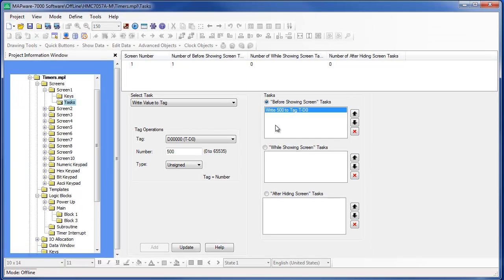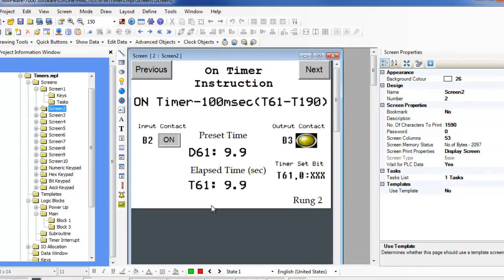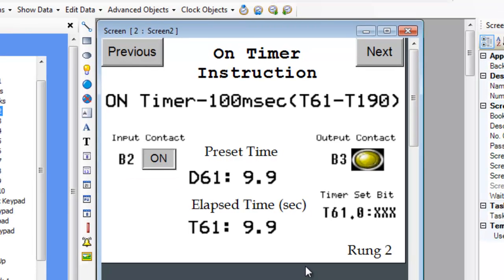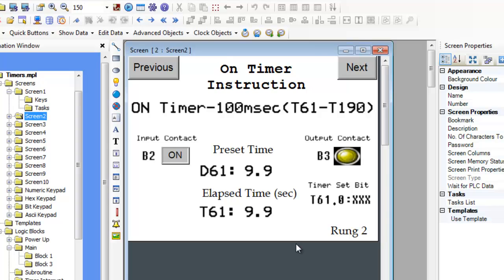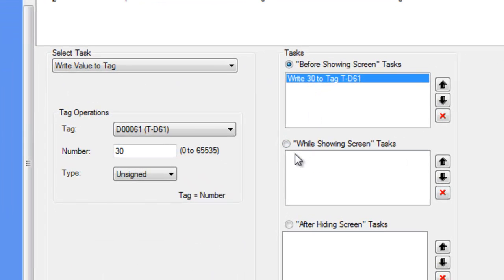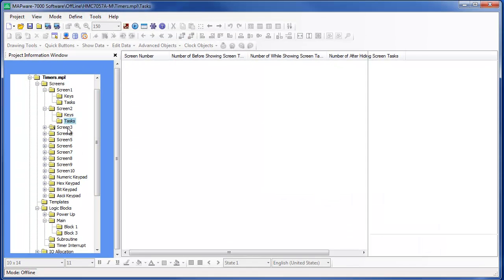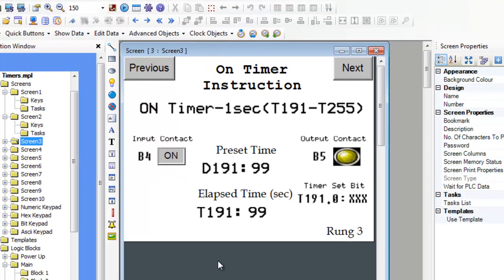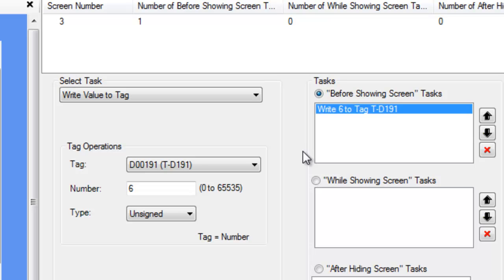Screen 2 demonstrates the operation of the 100 millisecond on timer in rung 2. The timer will start when the B2 toggle bit is pressed. We want the timer to count for 3 seconds, so in the task folder for screen 2, we preload D61 with 30 whenever this screen opens. Since a 100 millisecond timer always increments every tenth of a second, 30 is the proper value for a 3 second count. Screen 3 demonstrates the 1 second on timer in rung 3, starting when toggle bit B4 is pressed. Since we want it to count for 6 seconds, the task folder preloads D191 with 6.